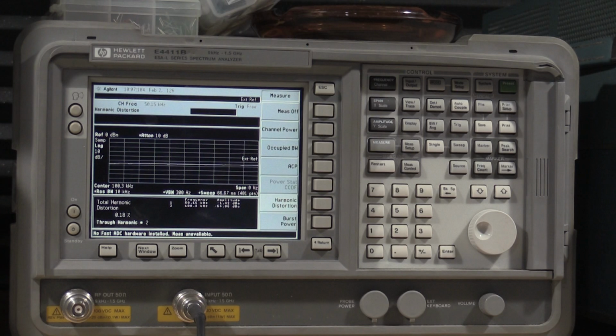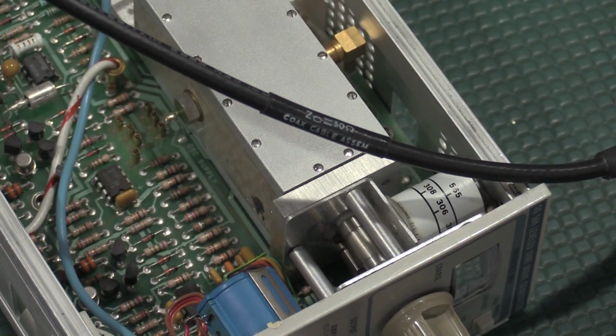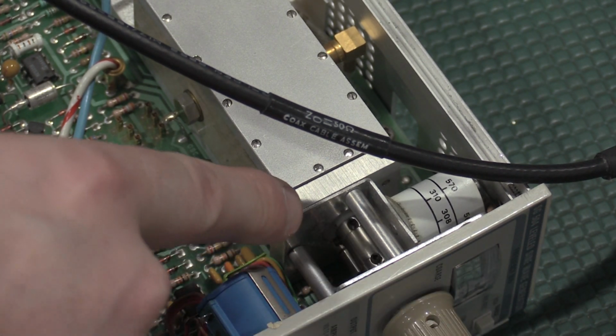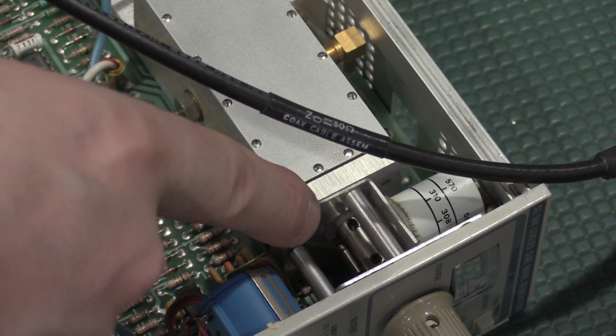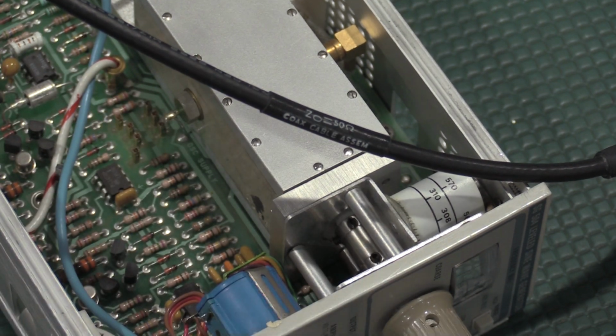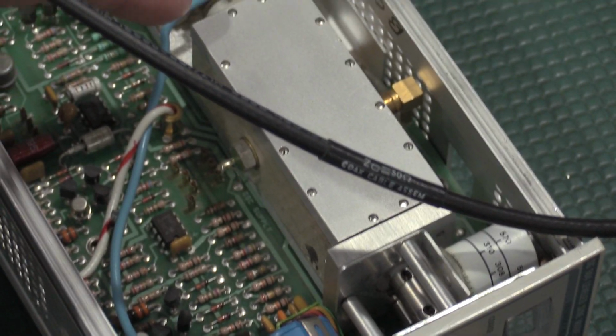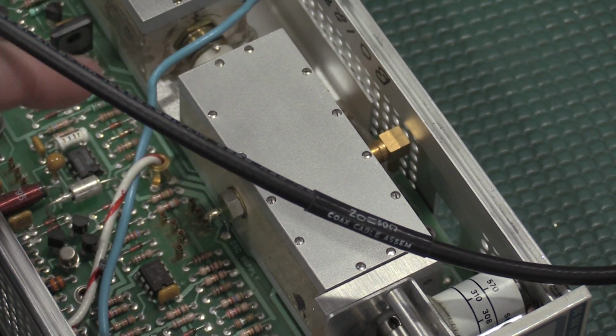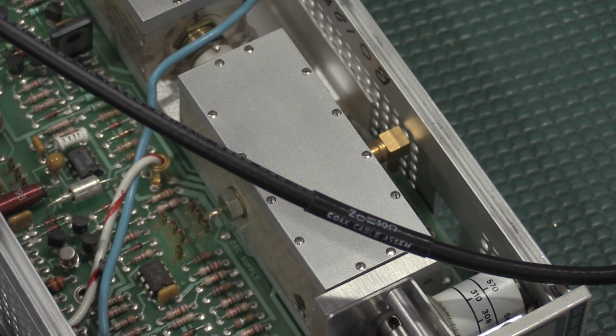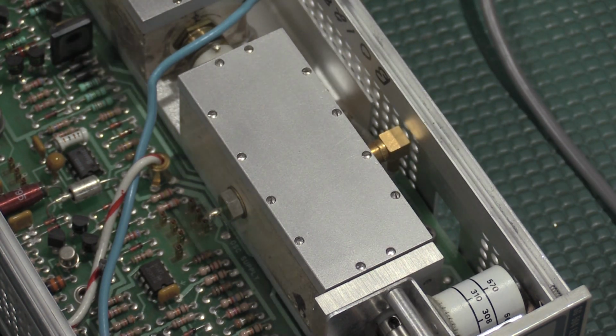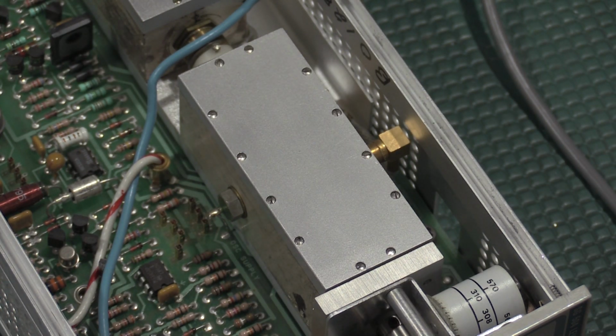For the frequency accuracy, I'm going to go back to the frequency counter. Okay, I'm going to have to do the mechanical alignment, so I have to loosen these two screws down here. We'll have to get in there with an Allen key, pop those loose. Then I have to rotate this control to get it into mechanical alignment. Then we'll have to do electrical alignment, and we'll have to go from there. But it is out of alignment, and the frequency is probably the critical aspect of this unit. So we're going to get it into alignment.